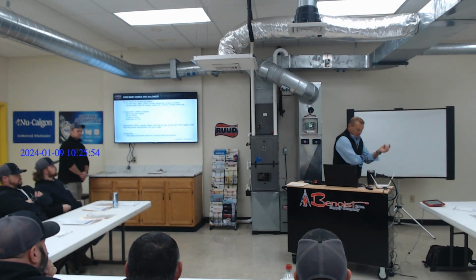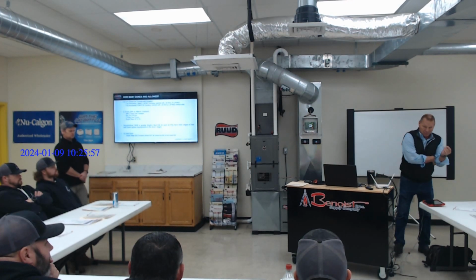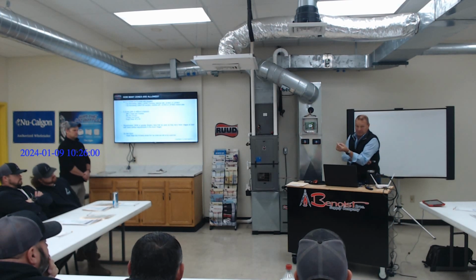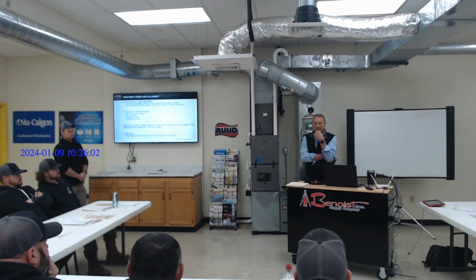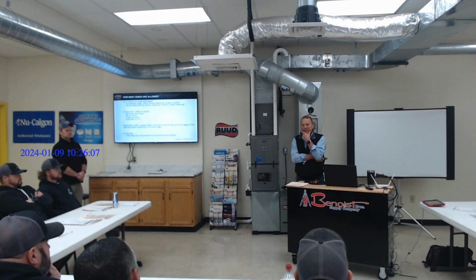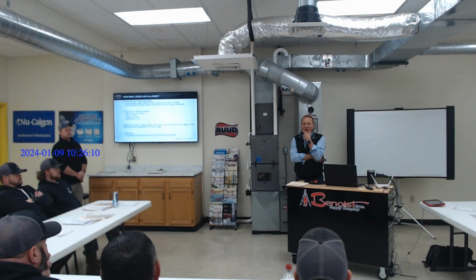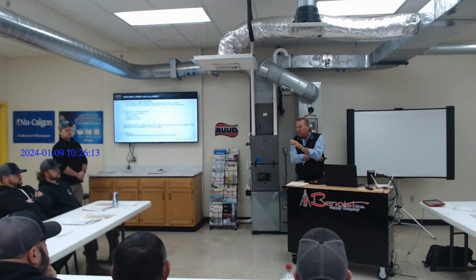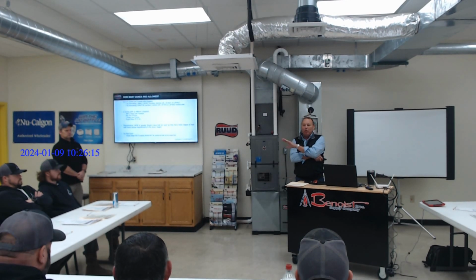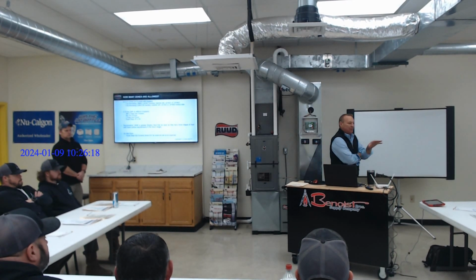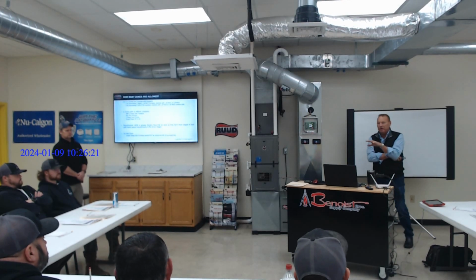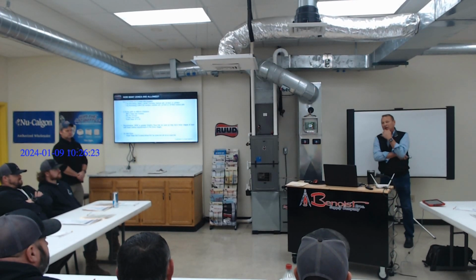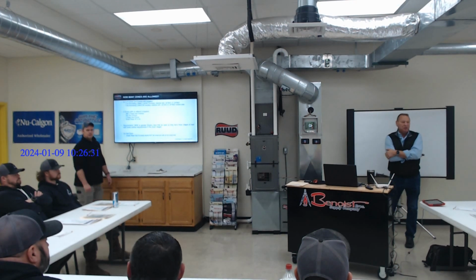The other thing to know that I should bring up is what is the CFM per ton we're using today in our high efficient equipment? Anybody know? 350? Yeah, it ain't 400. In some cases, I can get away with 325. So I got wiggle room with some airflow too, because I don't need 400 CFM specifically for this stuff to operate right. I've got a range from 325 to, I got some systems out there running on 300, and they're working because of the efficiency and because of the capacity of evaporative flow. So we got to keep that in mind too.